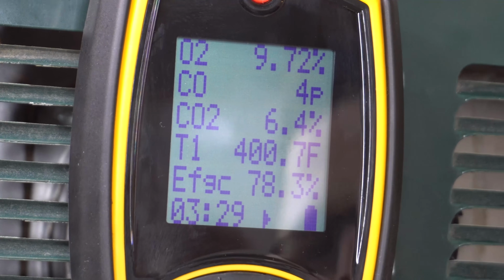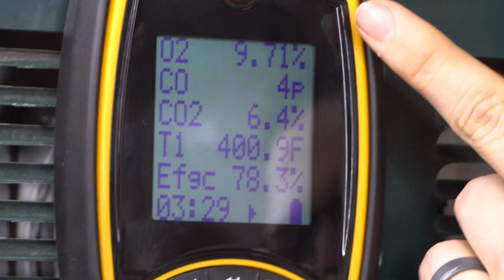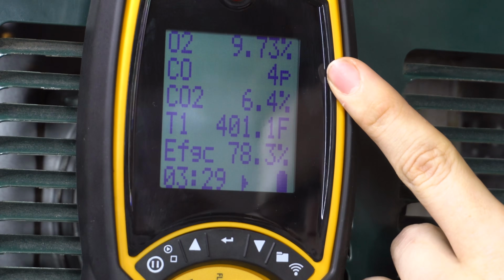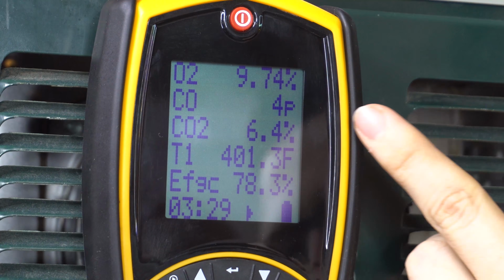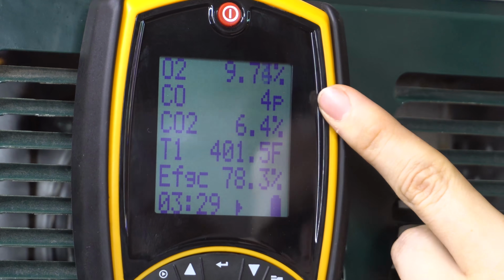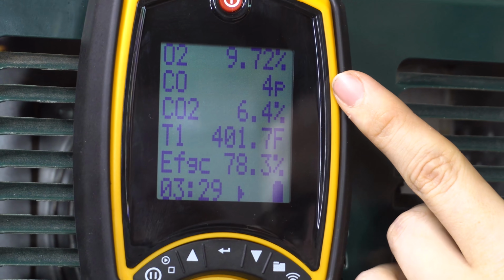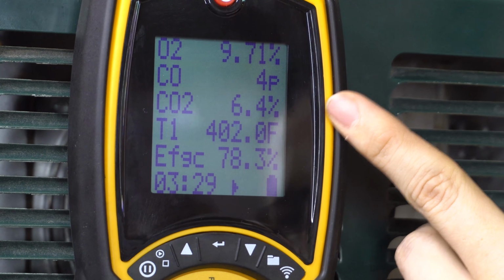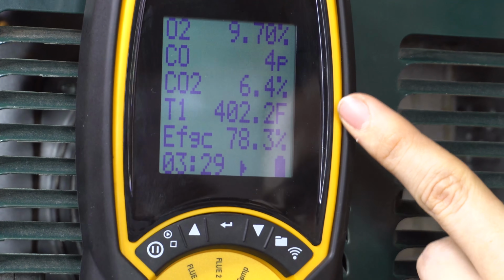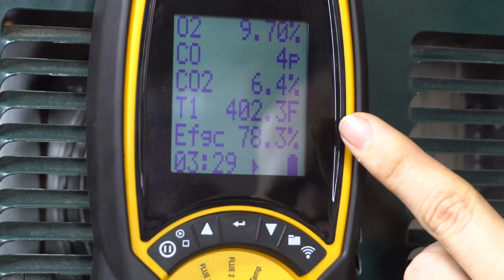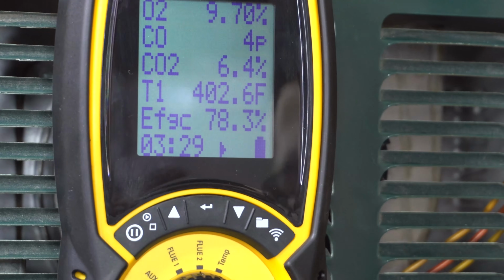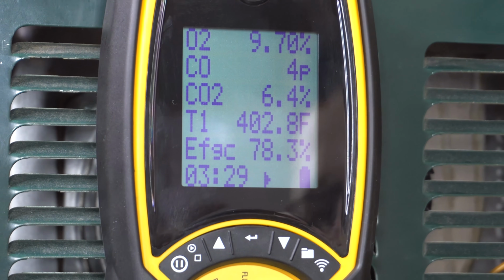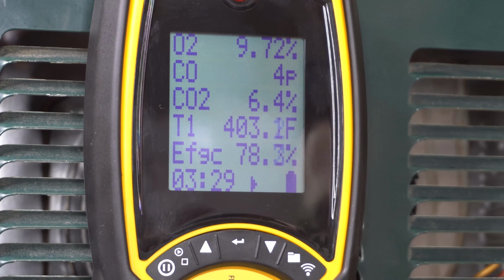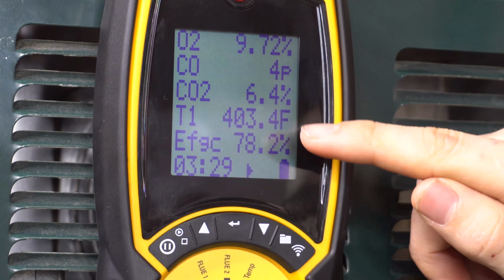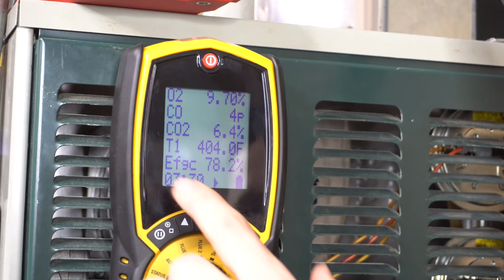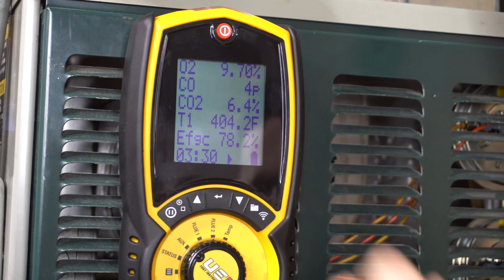So it's been about 3 minutes, and the numbers are pretty much stabilized. My oxygen levels dropped. Carbon monoxide surprisingly went down. Normally, I usually see it go up on the high stage, but going down is great. That means the furnace is actually burning very clean in its high stage. Carbon dioxide went up a little bit, and my stack temperature, or the temperature of my vent pipe, went up as well, up to 400 degrees, which is once again pretty normal for an 80% furnace. If you have an atmospheric draft furnace or a 70% furnace, the stack temperatures can get up to 500 or 600 degrees. And the efficiency stayed pretty much the same at 78%.